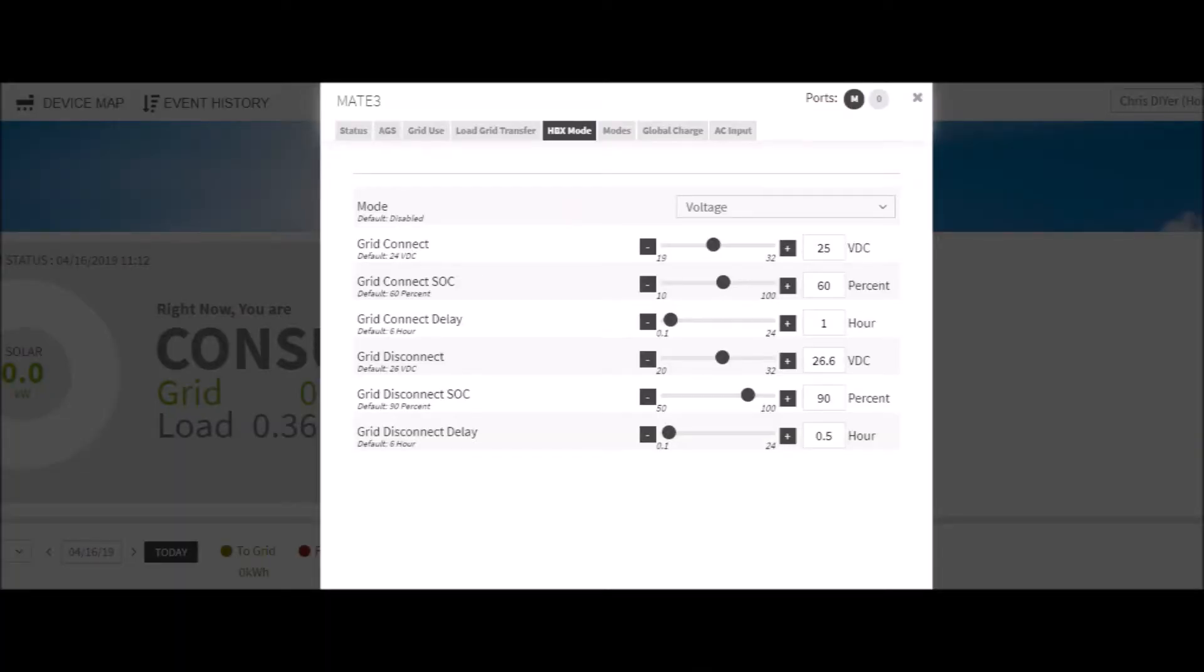All right, this is off the Outback Power Mate 3 HBX mode. As you can see, 25 volts for about an hour is when I connect back to the grid. It's when the battery bank gets down to 25 volts. And then I disconnect from the grid when it reaches 26.6 for about a half an hour.